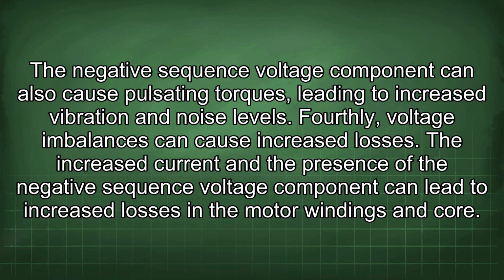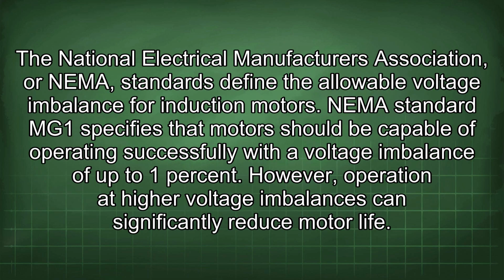Fourthly, voltage imbalances can cause increased losses. The increased current and the presence of the negative sequence voltage component can lead to increased losses in the motor windings and core. The National Electrical Manufacturers Association, or NEMA, standards define the allowable voltage imbalance for induction motors.